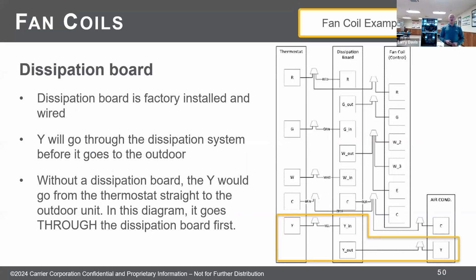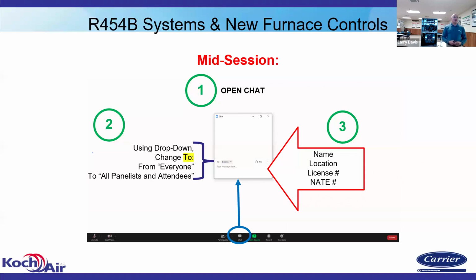Your Y call from your thermostat and your W call from your thermostat go through the dissipation board. It has second level priority before the system. And what I mean by that, if your thermostat gives a call for Y, the dissipation board has to say it's okay to run cooling before it'll bring the cooling on or heating. So the dissipation board shuts off your cooling and heating if it sees a leak and it's in the dissipation process.